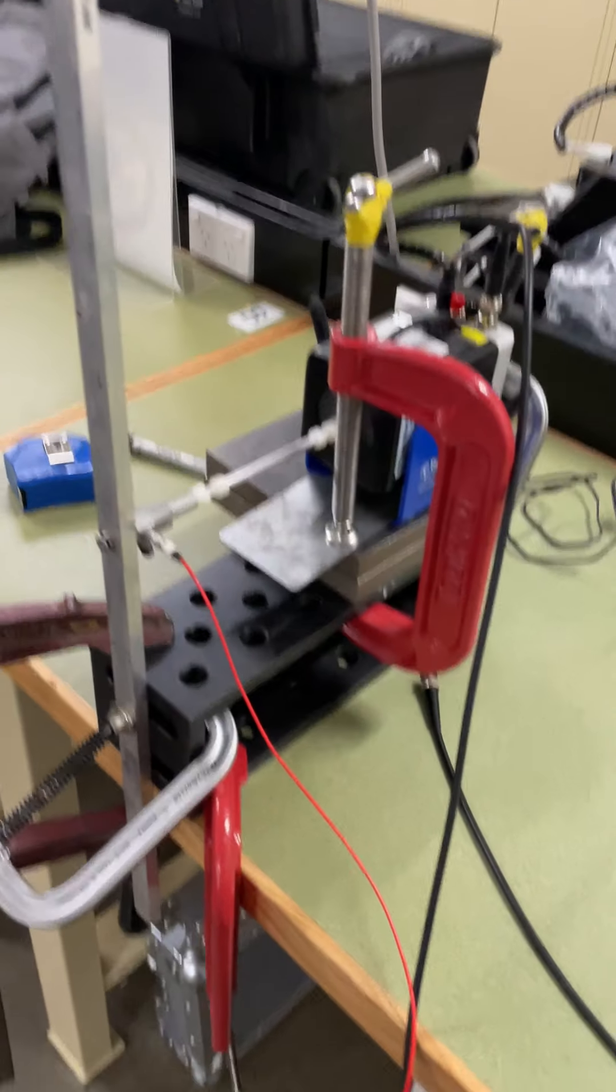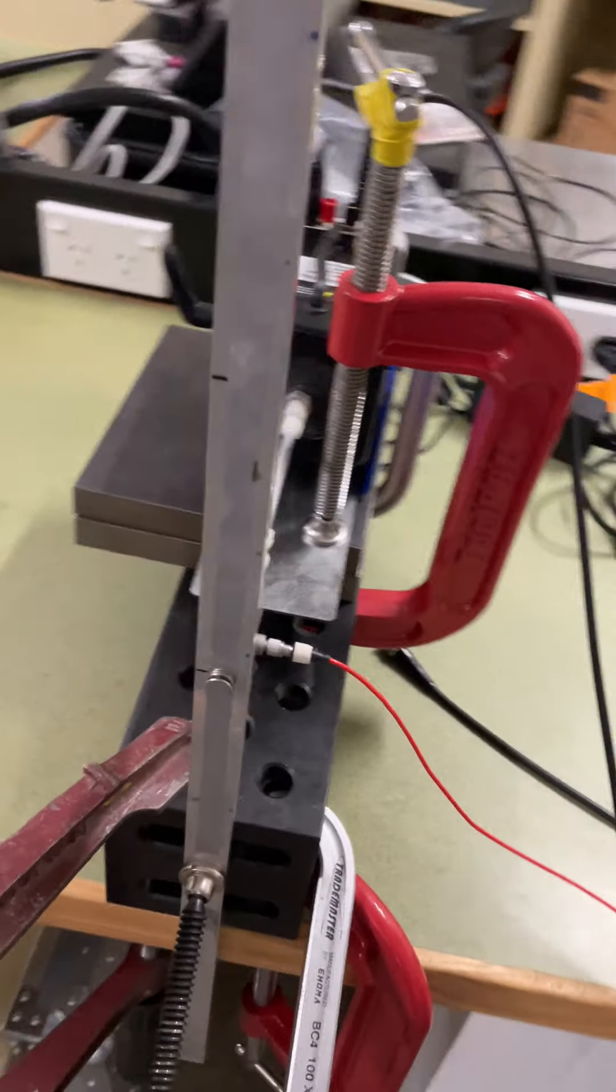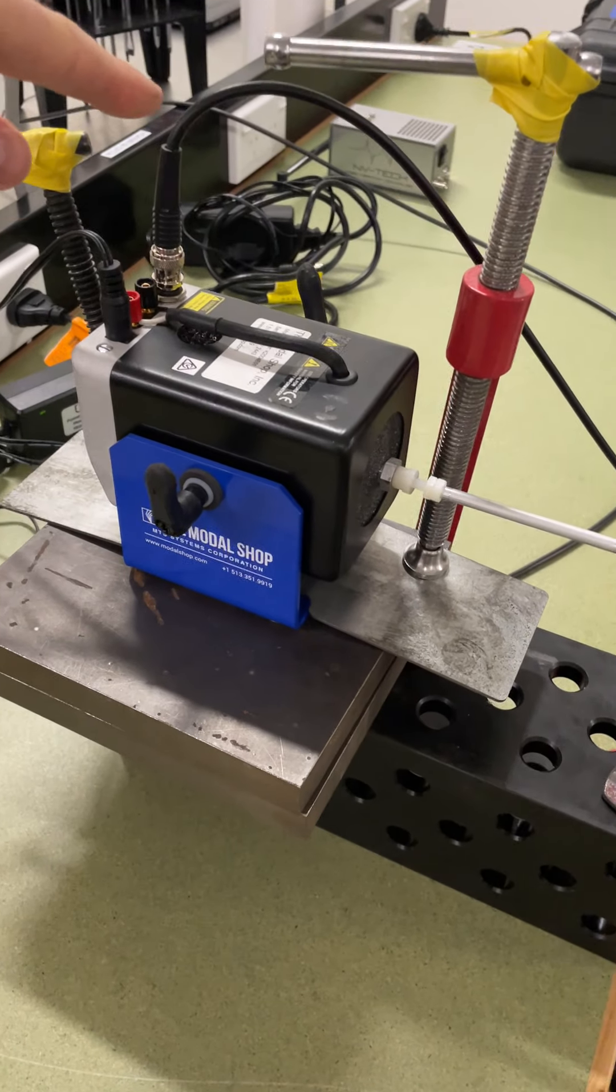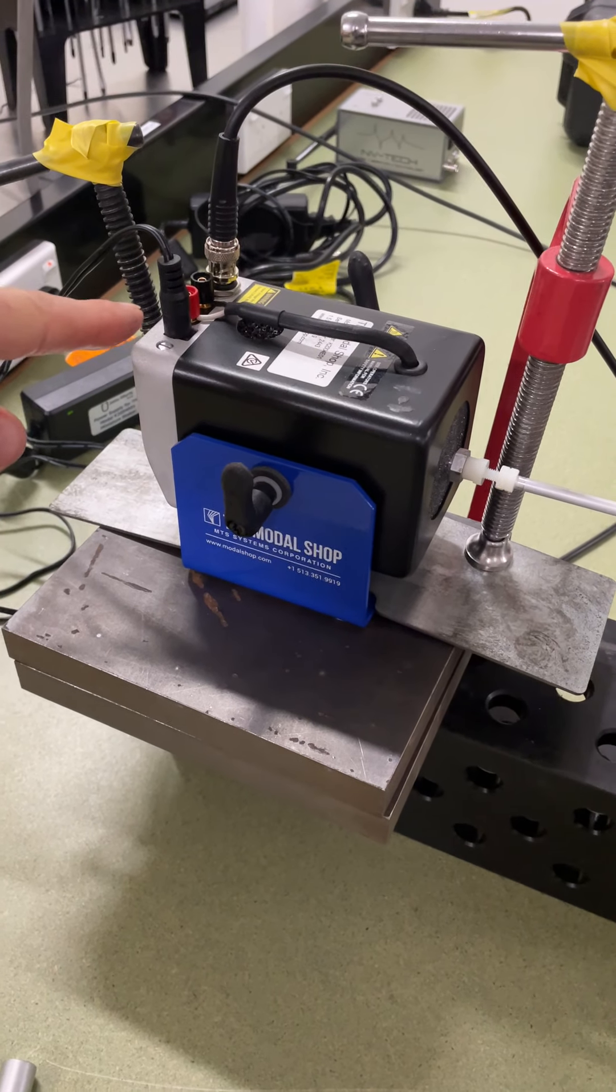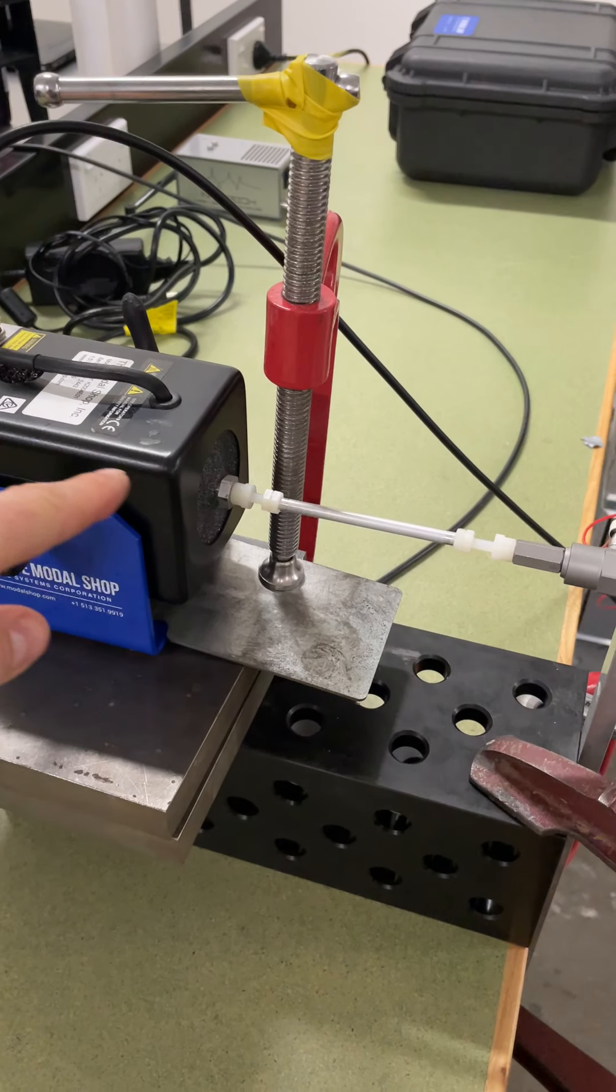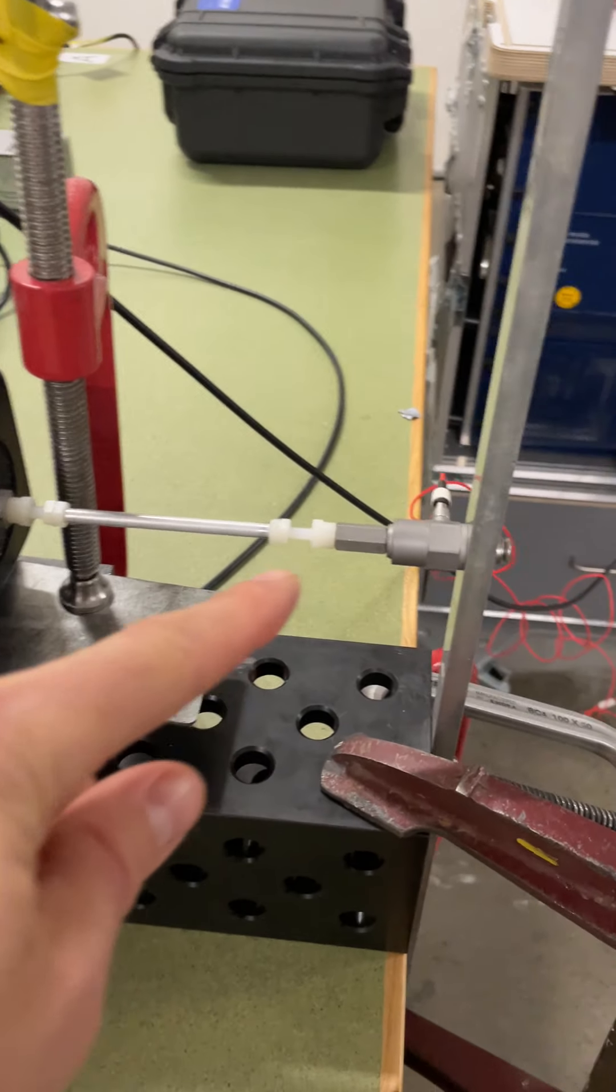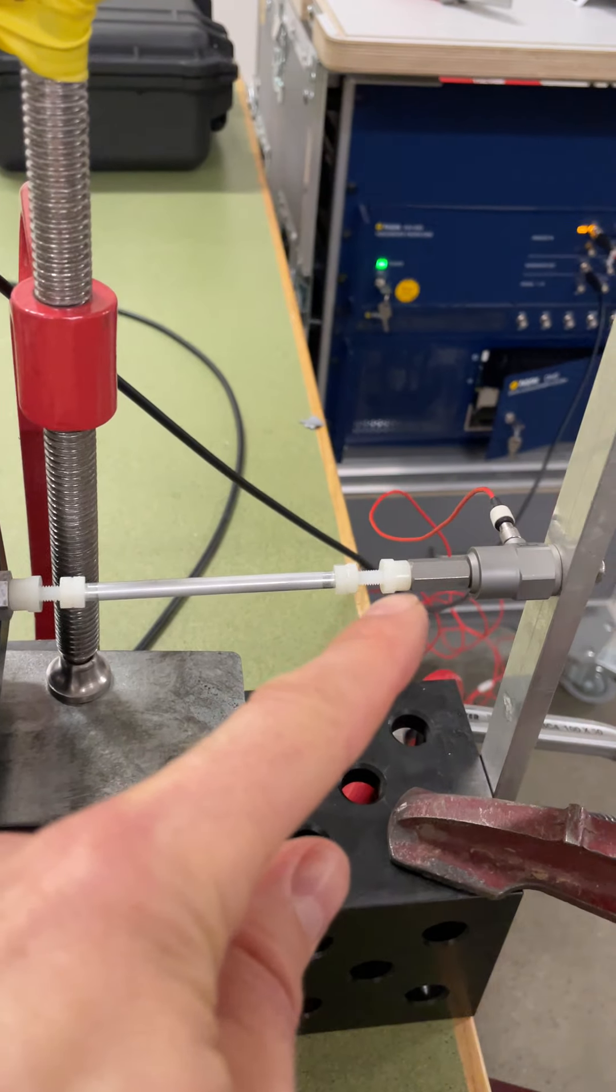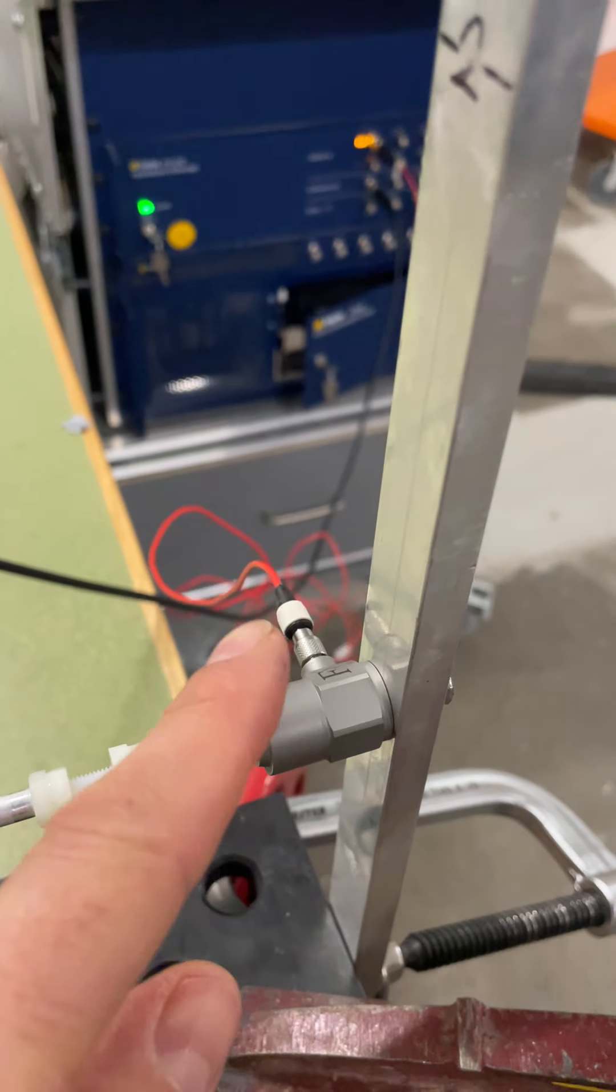You can see that we've got a shaker connected via a stinger arrangement to the structure and we're providing that with a signal from the laser vibrometer controller. It's got power and it's got a built-in amplifier here. It's essentially like a loudspeaker but a very precise electrodynamic shaker that's connected via this stinger which has got some flexibility in here to allow for a small amount of misalignment through a force transducer over here.